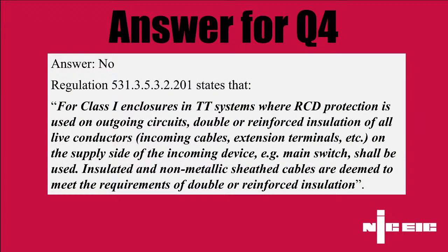It's one of them lovely long regulations. It rolls off the tongue. 531.3.5.3.2.201. So we got there eventually. And that particular regulation can be found on page 158 of the regs. But basically, the reason why is, if you've got that class 1 enclosure in a TT system, it's all about the methods of protection of double and reinforced insulation. So if you have got double or reinforced meter tails, for example, coming to the enclosure, where the outer sheath isn't cut back and it's going straight into the incoming device, that will protect you for basic and fault protection for that part of the installation, and that's why an RCD isn't required if you have got that measure.